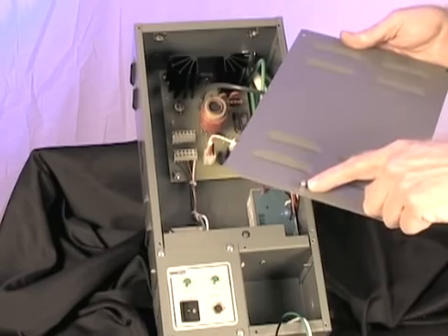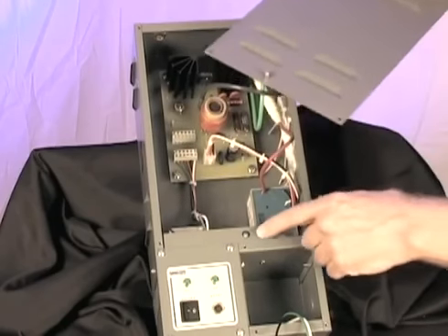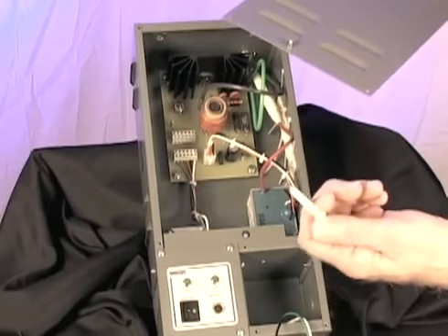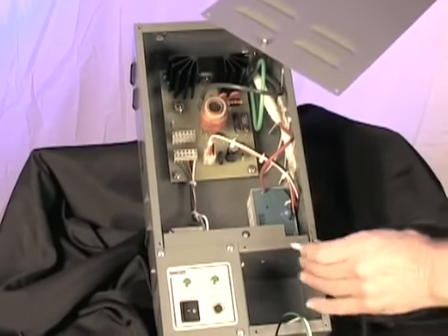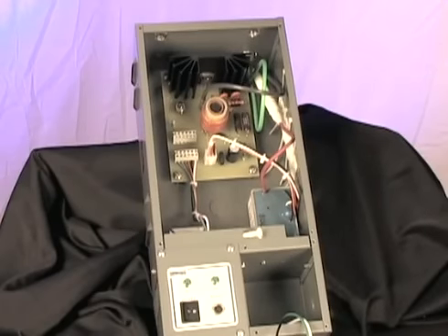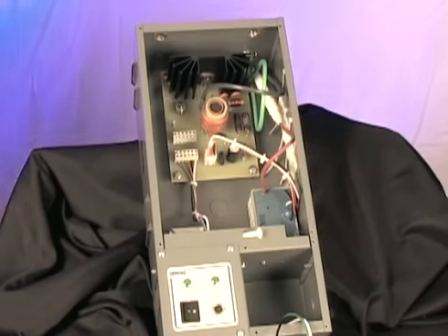This allows you access to the electronics, and you'll notice that on the bottom of the lid there's a plunger. This is to actuate the micro switch. If you have anything like this phenolic screw or a screwdriver, you can push it right into here. This will actuate the micro switch and provide the power to the internal electronics so that you can troubleshoot.